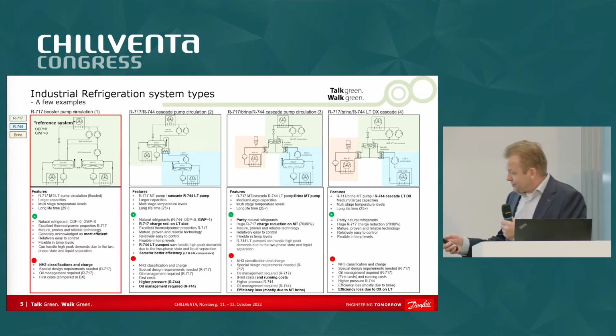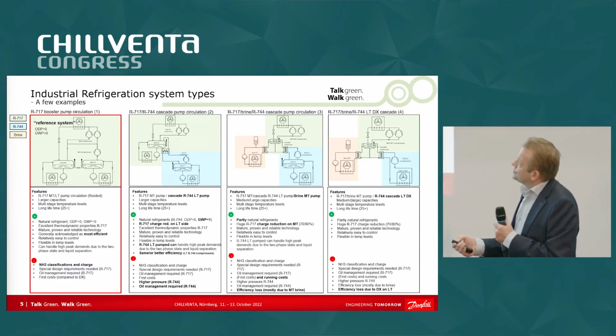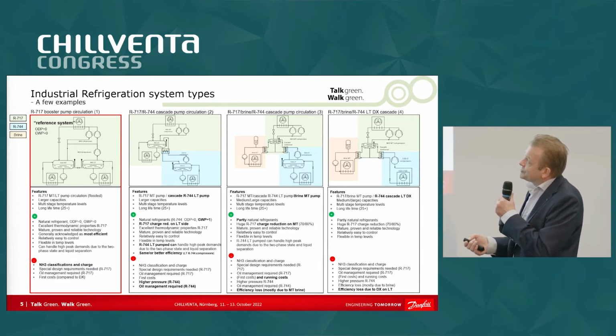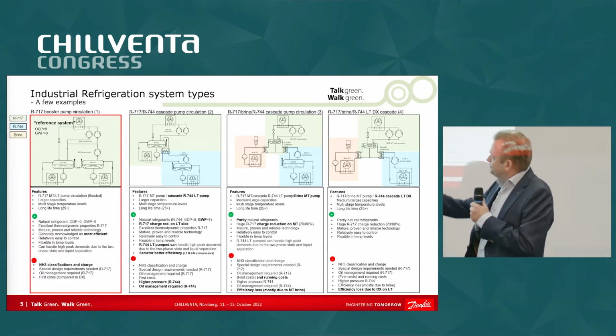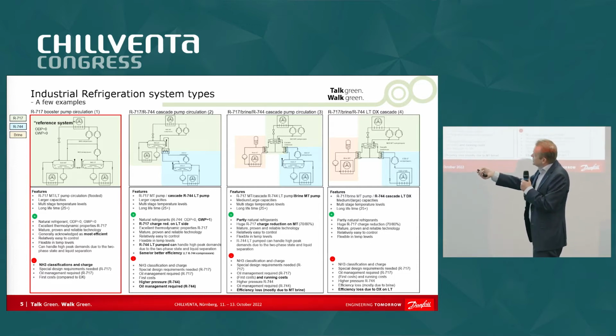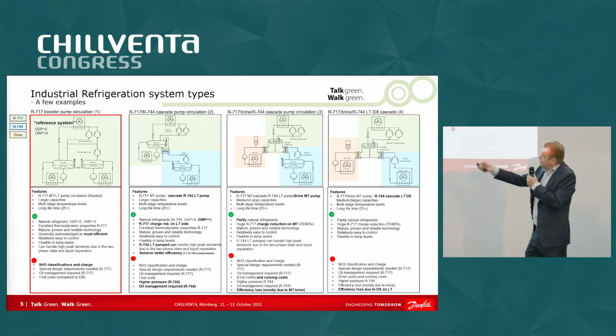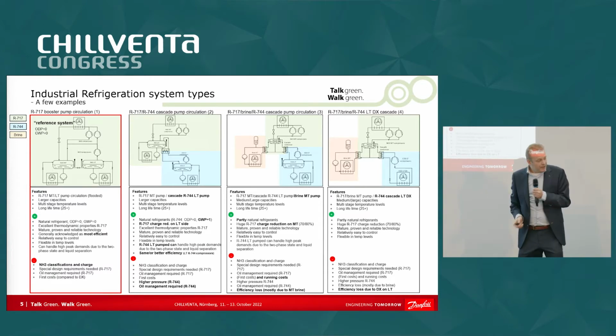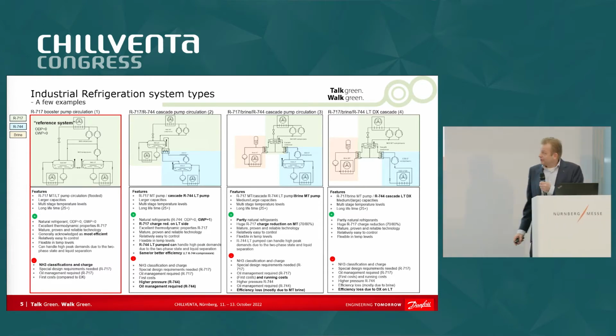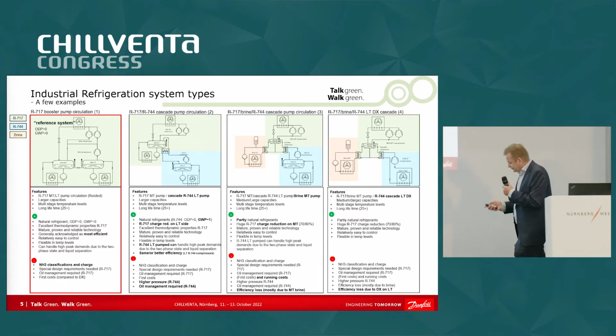Okay, so here are the systems. So this one is the typical reference ammonia system. We have medium temperature separators, low temperature separators, and pumps. So you pump more ammonia through the system than you really need. So you have flooded systems. Here we have low temperature ammonia compressors, medium temperature. So this is the reference system, very robust, works very well. And this is the system that we compare everything with.